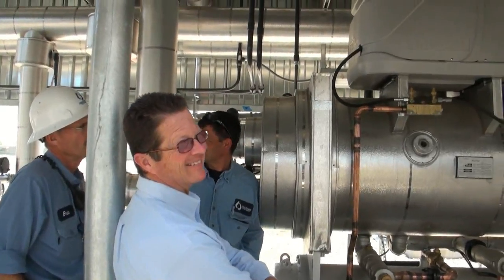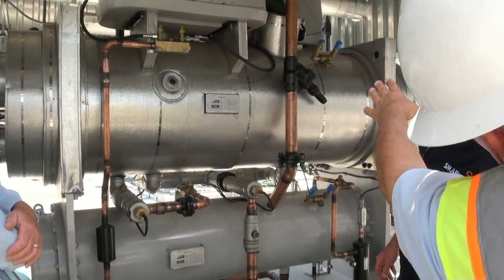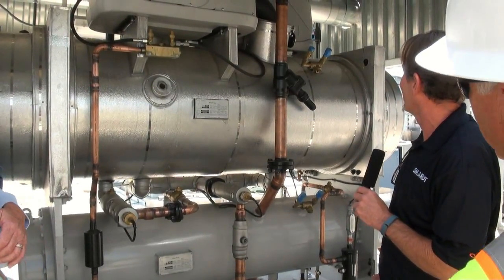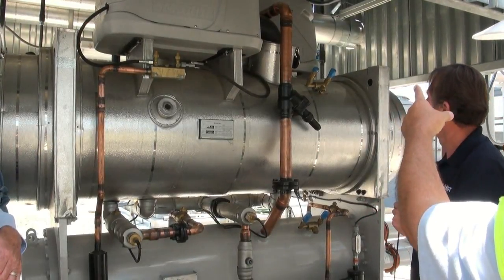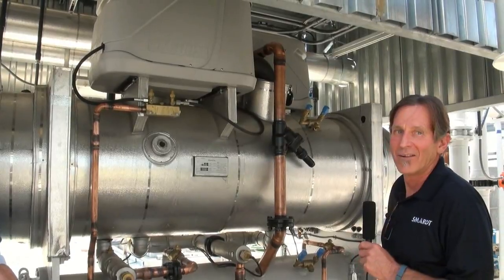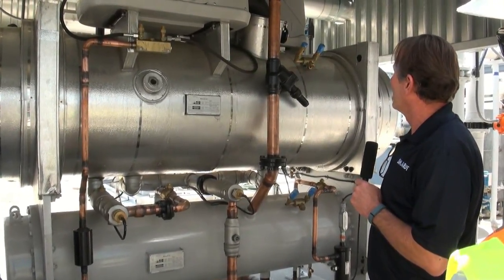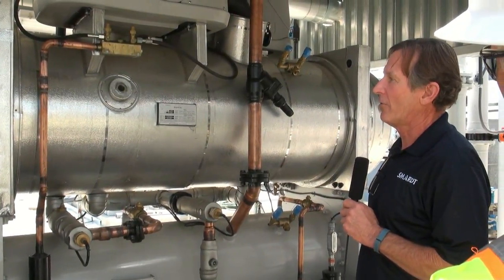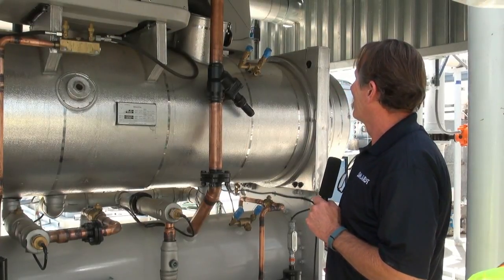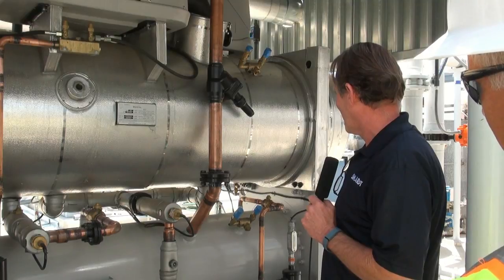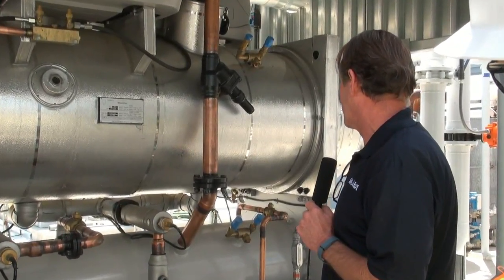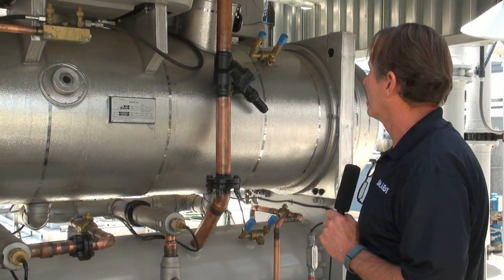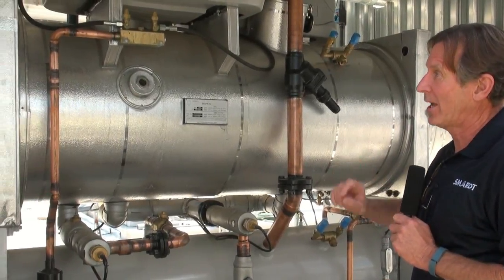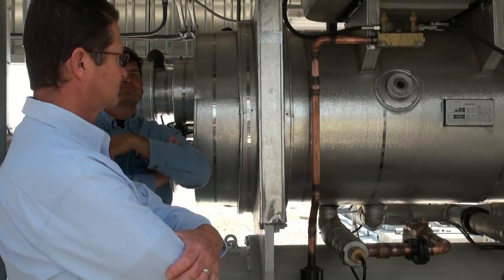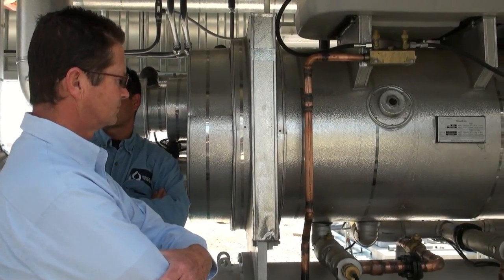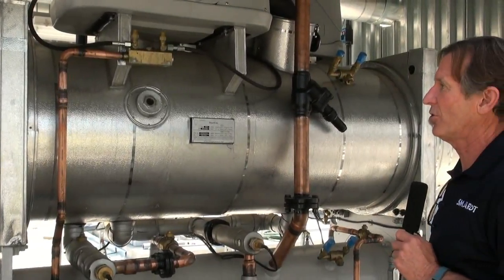Speak right into the microphone. So with the yellow tape, the blue tape, what is that? I don't know. That's not factory. We brought that up to the contractors. What are they? They're relief valves. Oh. If the relief valve opens, that tape won't stay there very long. Yeah, these ones aren't even working because you'd kind of hit somebody right in the head. It's probably not. I don't know. It is what it is. But I guess it's to keep debris out. A lot of applications you see a plastic cap maybe on there to keep the dirt out. I'm hoping they're going to stand them somewhere else. Just a short pipe and an inverted U would probably be fine.